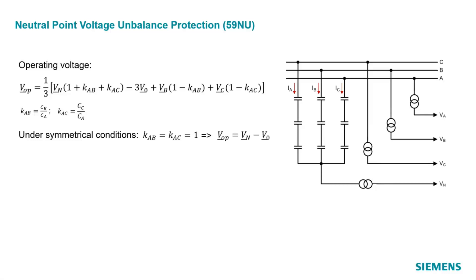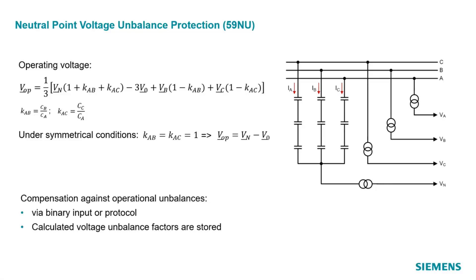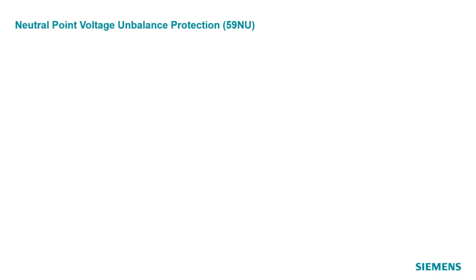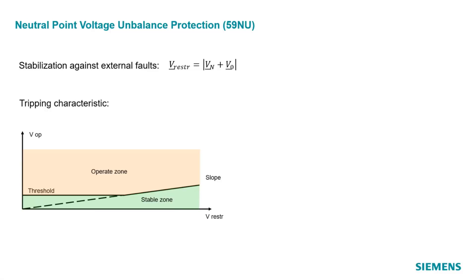However, also with this method we experience an influence of operational unbalances of the capacitors, so that VOP can be different from zero and hence compromise the calculation result. Thus the function has a built-in compensation feature which calculates the voltage unbalance factors based on the momentary measured voltages and stores them in a non-volatile memory. These values replace the values of 1 used before compensation. For external faults, where the voltage of one phase can break down and the neutral voltage reaches a high value, the operating voltage can be different from zero because of measurement errors for the voltage transformers. That is why tripping by VOP is stabilized with a second quantity called the restrained voltage V-restrained, calculated as the absolute value of Vn plus V0. Similar to current differential protection, a tripping characteristic is defined between the operating voltage VOP and the restrained voltage V-restrained, with a threshold and a slope as parameters.